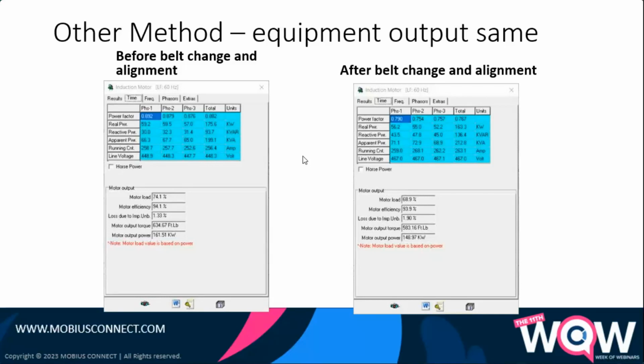Now we take a look at a grosser one. This is one where we had 10 D belts on a pulley, and we brought in a belt manufacturer, and they brought it down to 2 modern V belts, and just slightly larger pulleys. So we had to make some other modifications. But this is an actual application that reduced the total load. By the way, the output was exactly the same, from 74% to 68.9% load on the motor. So it had a just over 5% drop in load. And this is the same machine. We saw the output 161.1 down to 148, 175 kilowatts to 163 kilowatts.